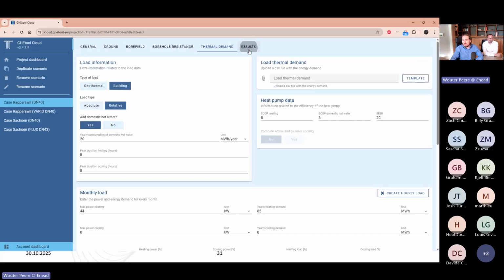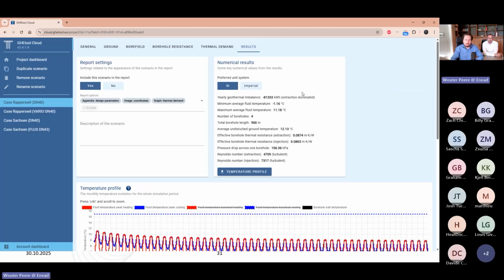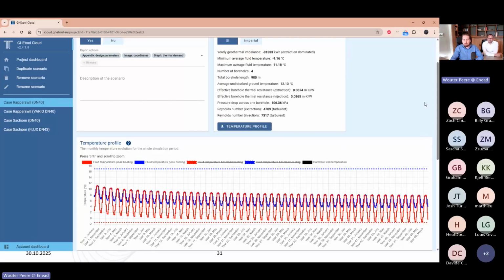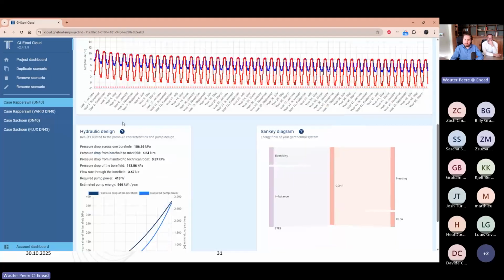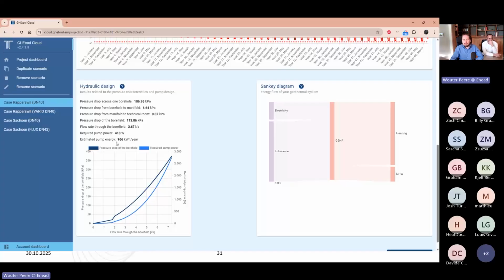So if we then go to the results, we have a couple of numerical results here. We see that we go towards minus 1.16 degrees after 50 years, which is above our design limit, so it's well designed. We are in a turbulent regime, and the pressure drop across our single borehole is 107 kPa. Or if we scroll down, we see the hydraulic design, and we see that we have here an estimated pump energy of around 970 kilowatt hours per year of electricity consumption for the pump.